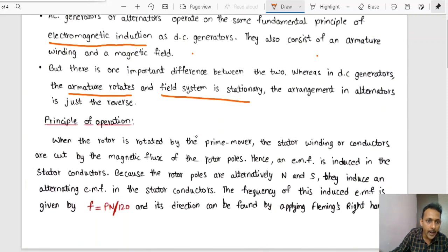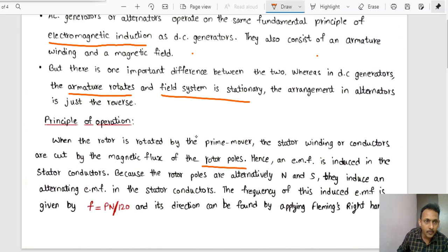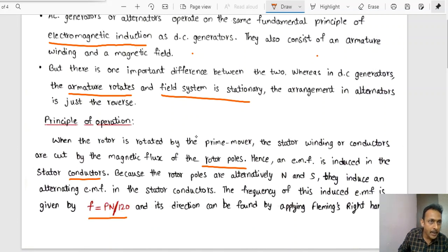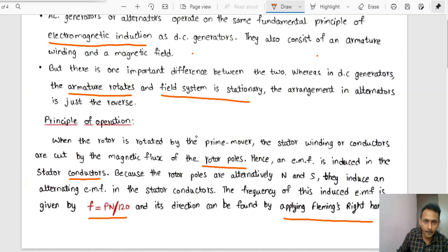As the rotor is rotated by the prime mover, the stator winding conductors are cut by the magnetic flux of the rotor. Because of this, an EMF is induced in the stator conductors. The induced EMF frequency is given by f = PN/120, where P indicates the number of poles and N indicates the speed in RPM. The direction can be found by applying Fleming's right-hand rule, and due to this induced EMF, current will flow.